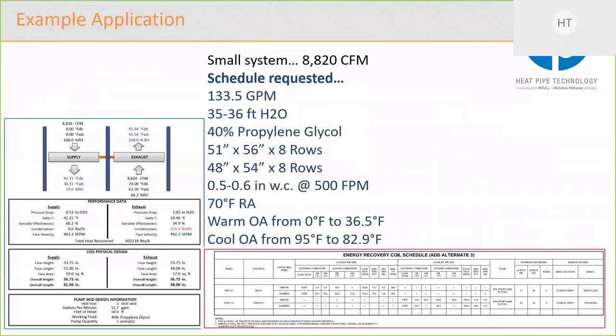So this is what we came up with. The graphic on the left is an example of what our performance output would look like, and this is what we proposed. First of all, our system is lower gallons per minute. If you think back to the coil design where I was talking about the paradigm change, this is where you start to see the differences. We're using a slower fluid flow through our coils, and that means lower gallons per minute. We had a little bit more head, it's 50 feet. However, when you look at the gallons per minute and the head combined, the pumping power is actually 43% less than the original schedule required.